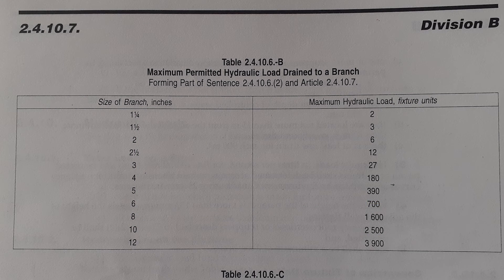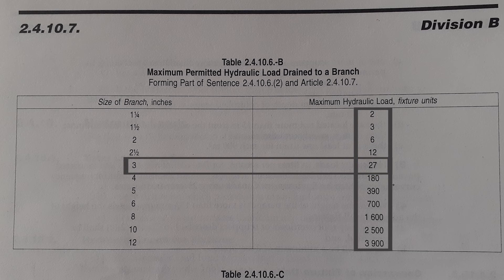Let's have a look at how to use these. The branch table is super easy to use. The left-hand column is the size of branch in inches and the right-hand column is the corresponding fixture units you can drain down those pipes. For example, if I have 25 fixture units draining through a branch, I look at the right-hand column. I have a choice of 12 or 27 fixture units. Since 12 is not big enough, I go to 27, and the corresponding size is 3 inch.